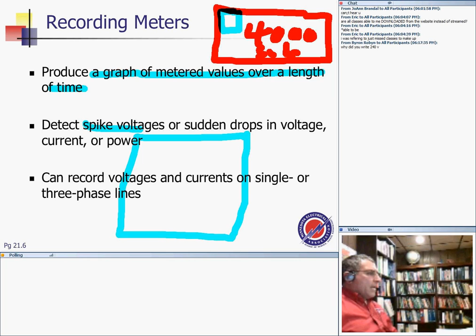all of a sudden it went all the way up to the sky and came down, that's a spike in the voltage, and it shows you this spike. So then you can go down to your plant and analyze it and see that every time you start this chiller, it creates this resonant effect in the system, so you might have to go solve this problem. It gives you the signature of everything that goes into your plant.